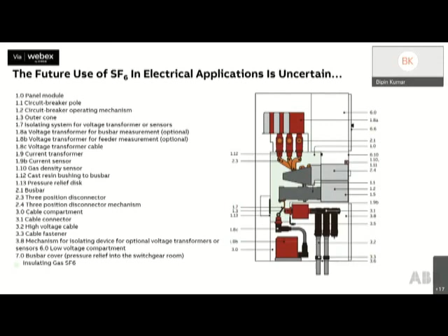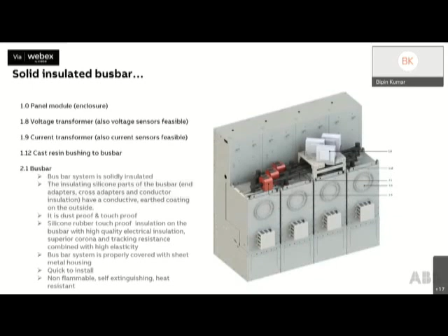This particular GIS uses a single tank where you have only the circuit breaker, but the bus bars are taken outside the gas tank. So you can access the bus bar in case you want to, but these bus bars are touch proof. The surface potential of this particular bus bar is at zero, so it is accidentally touch proof, and also gives you very flexible maintainability.